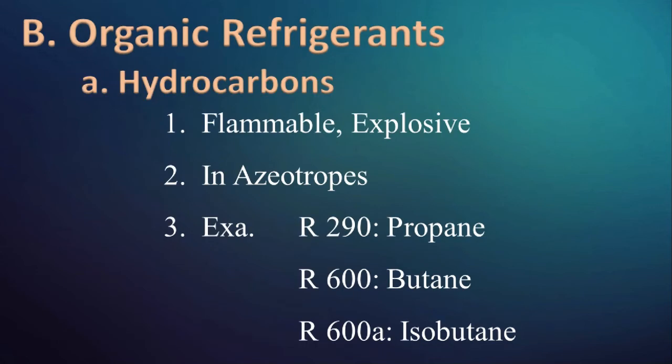Now let us see organic refrigerants. The first one is hydrocarbons. Hydrocarbons are flammable and explosive. Depending upon thermal properties like evaporation temperature and pressure, they are used in various industries, nowadays even by combining with other refrigerants, which are known as azeotropes. Some popular hydrocarbon refrigerants are R290 propane, R600 butane, and R600A isobutane.